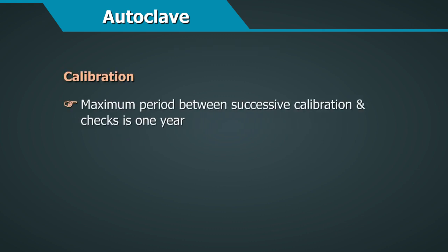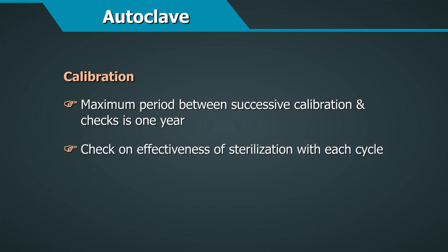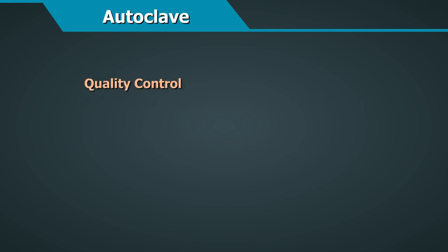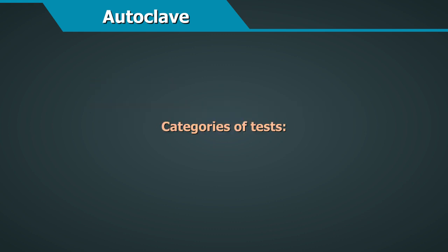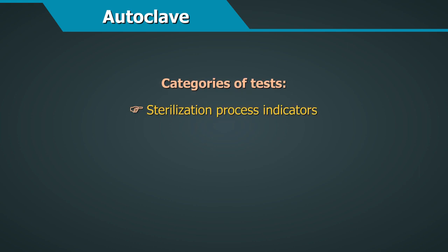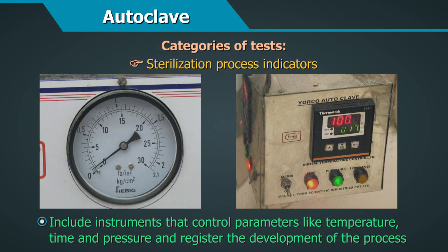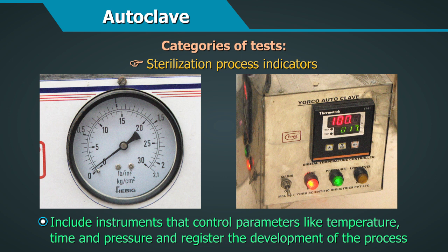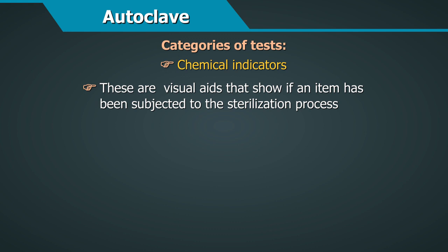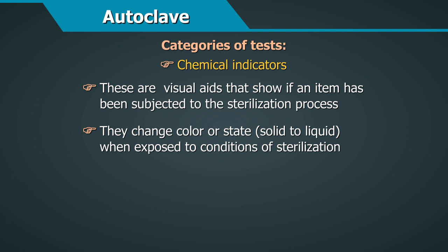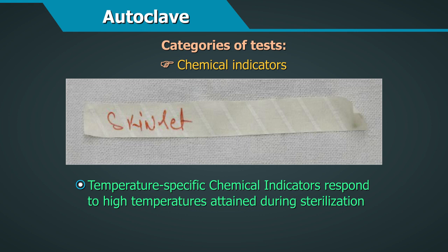The maximum period between successive calibrations and checks should be one year, with effectiveness of sterilization checked with each cycle. For quality control, different categories of tests are used. Sterilization process indicators supervise the functioning of autoclaves by controlling parameters like temperature, time, and pressure. Chemical indicators are visual aids that show if an item has been subjected to the sterilization process — they change colour or state, such as solid to liquid, when exposed to sterilization conditions. Temperature-specific chemical indicators respond to high temperatures attained during sterilization.